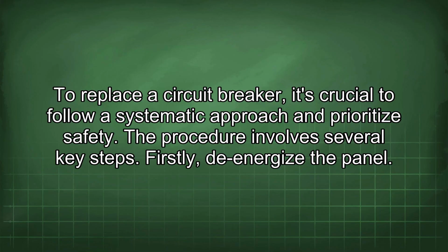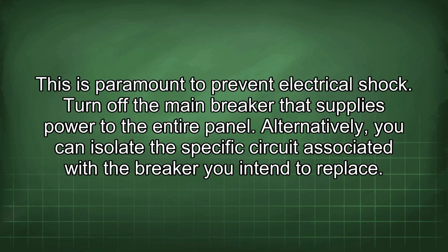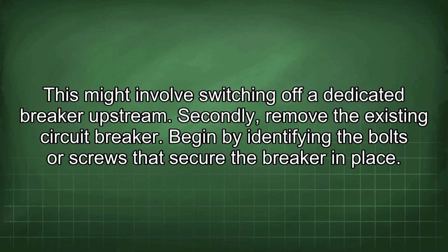To replace a circuit breaker, it's crucial to follow a systematic approach and prioritize safety. The procedure involves several key steps. Firstly, de-energize the panel. This is paramount to prevent electrical shock. Turn off the main breaker that supplies power to the entire panel. Alternatively, you can isolate the specific circuit associated with the breaker you intend to replace. This might involve switching off a dedicated breaker upstream.